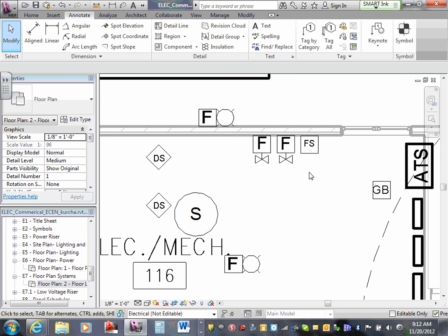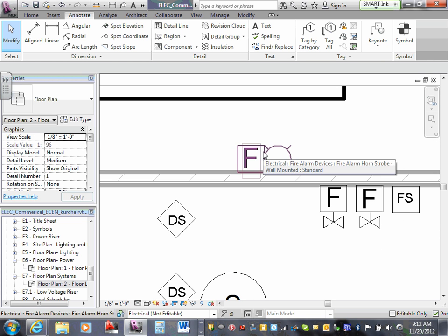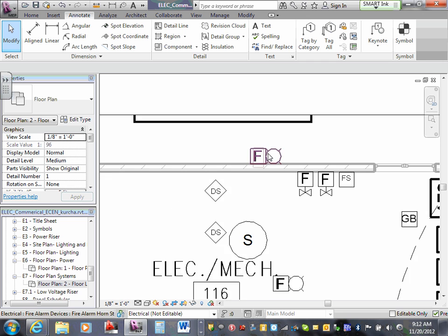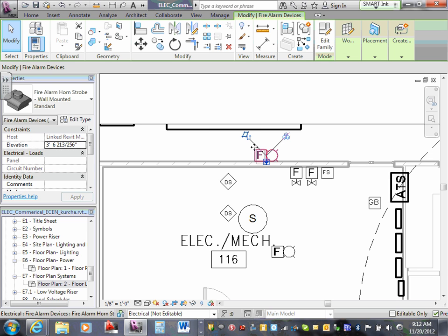The fire protection horn strobe located above the Siamese connection on the exterior of the building is right outside of your main fire sprinkler assembly. So you've just got a horn strobe that basically shows the fire department where they can hook up to the Siamese connection. So if they pull up to your building and they see that horn strobe flashing on the back of the building, they know that if they want to hook up, they need to go back there.